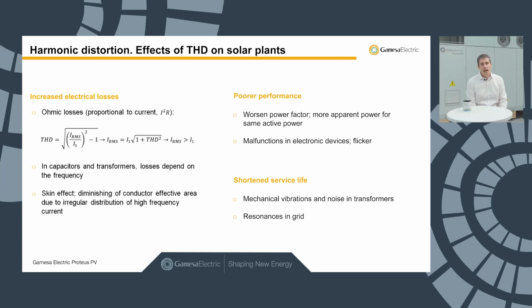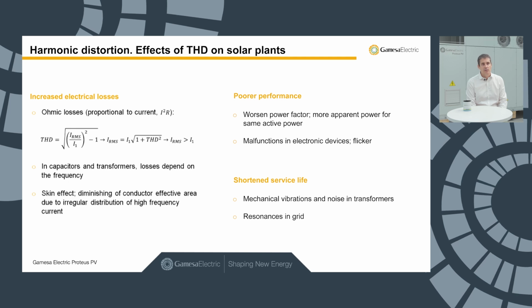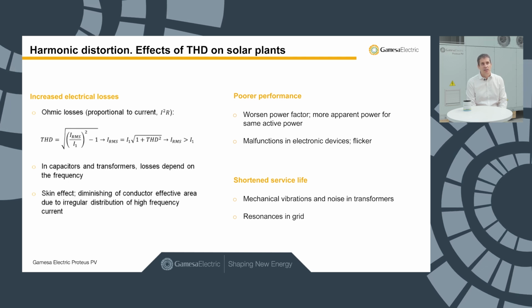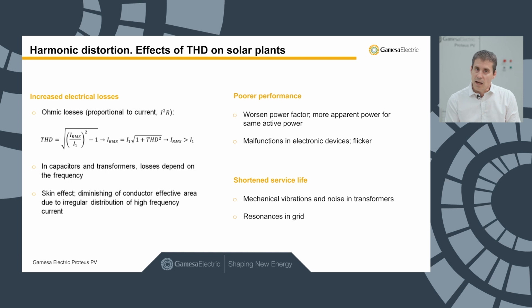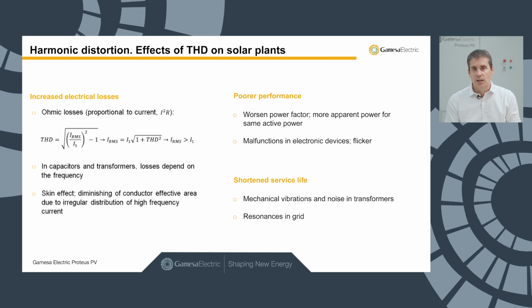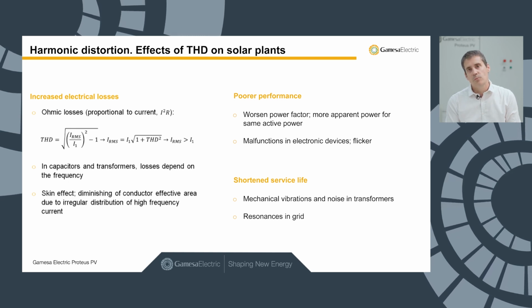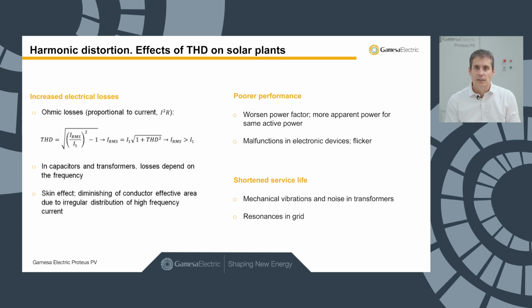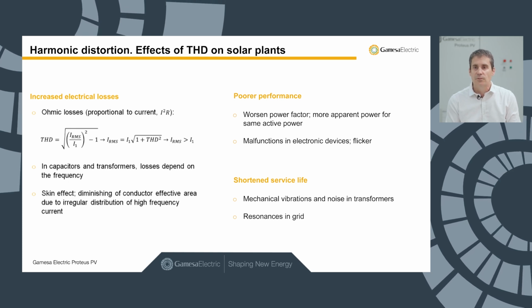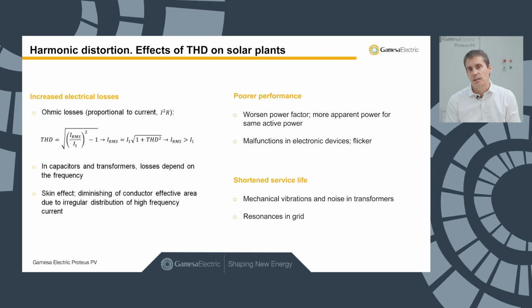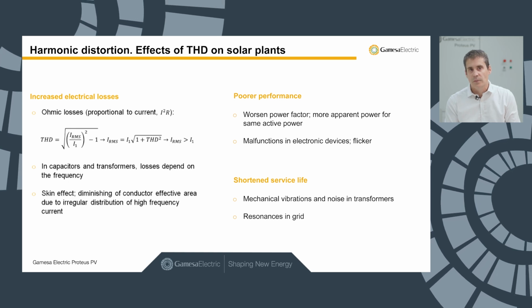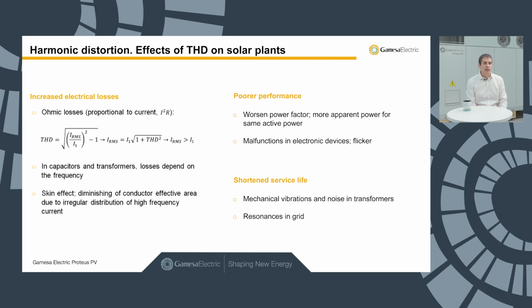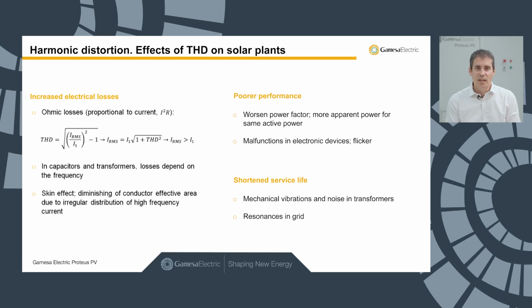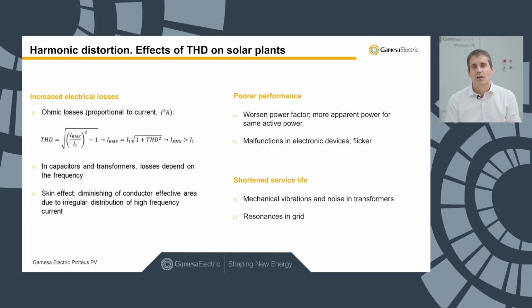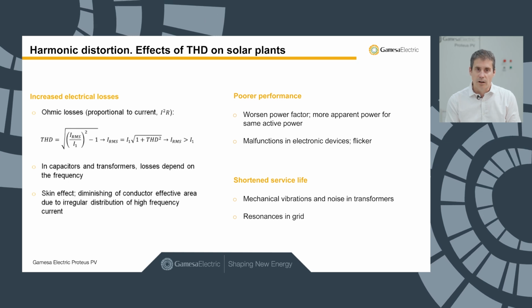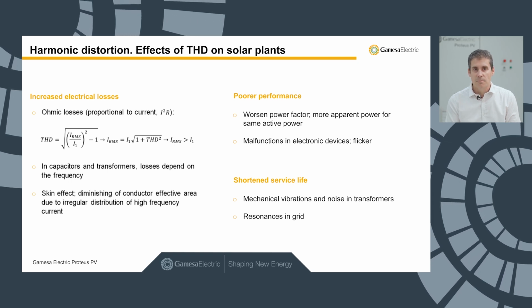Basically, we have three main effects on the solar plant from the total harmonic distortion. We will have an increase in the electrical losses. We will suffer poor performance of the solar plant, and we will shorten the service life of the components, such as the transformer installed there. We will suffer an increase in electrical losses by means of ohmic losses, proportional to the square of the current multiplied by the resistance.